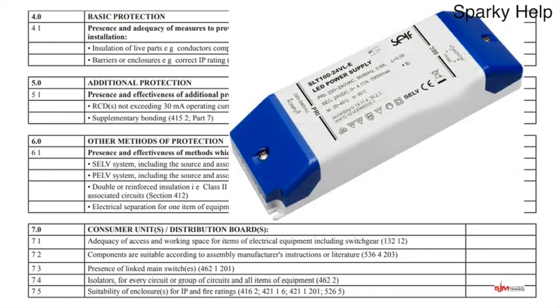Then we've got other methods of protection, and it breaks it down to SELV. So SELV, if you've got alternative supplies. So what does SELV stand for? It stands for separated extra low voltage. So this is below 50 volts AC as an output voltage or below 120 volts DC. So as you can see, this is for LED power supplies. A lot of these will be integral within the fittings themselves, but if you put in extra external drivers in, then this would be the case. If you're fitting these, then it will be a tick.